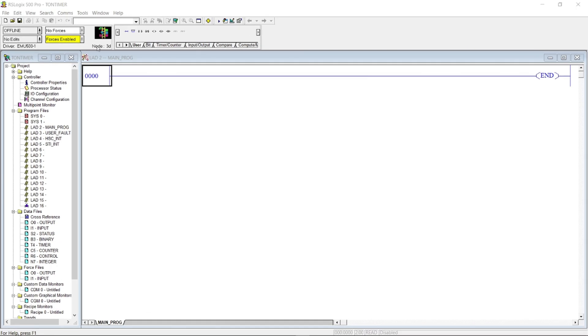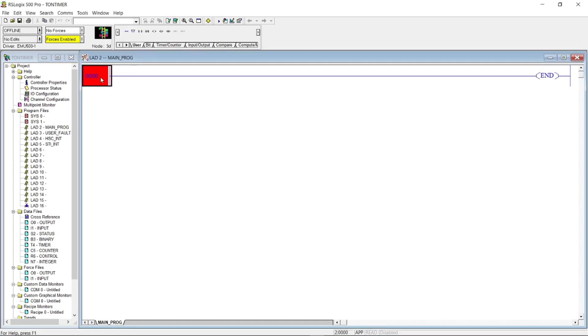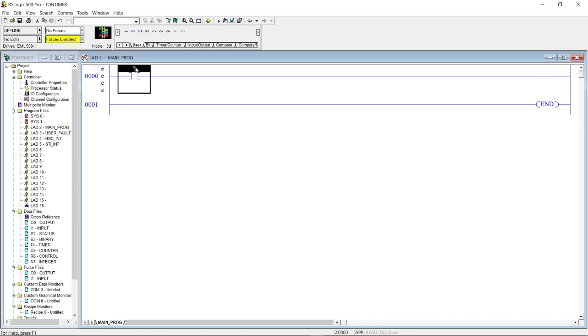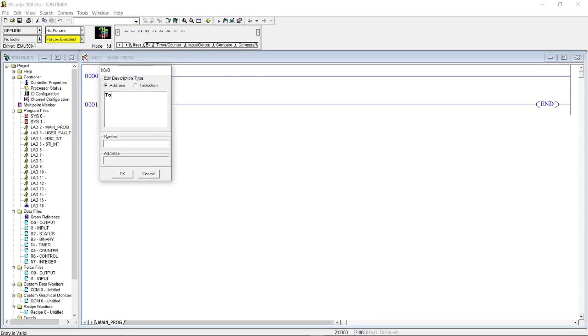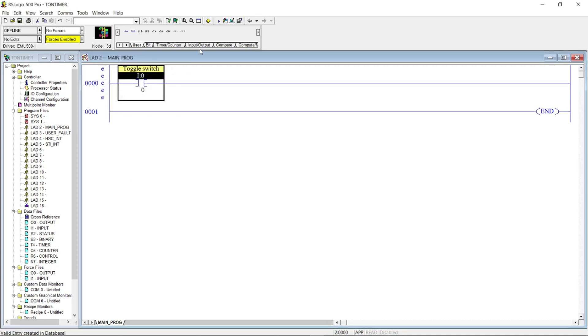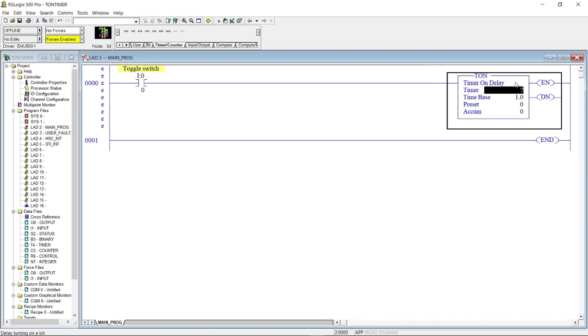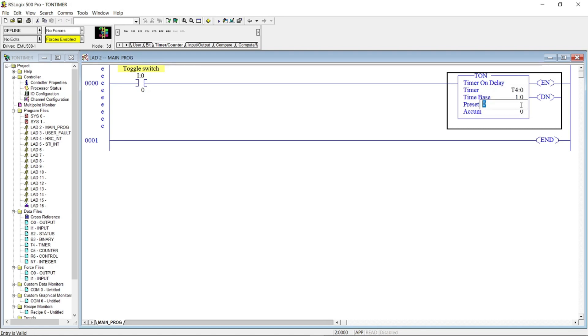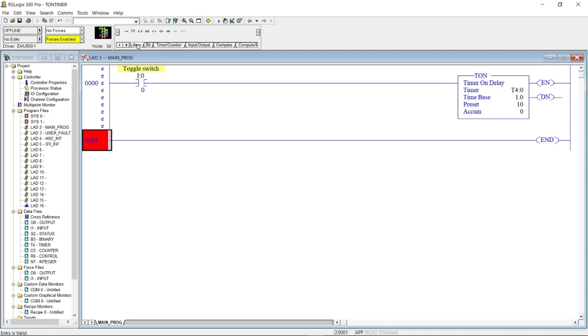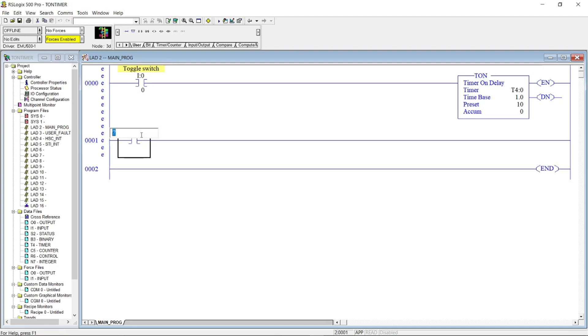Let's make a PLC program using the Timer On Delay. We'll put an open contact for a toggle switch, then drag in the Timer On Delay instruction. We will put the address for the timer as T4:0, and for the preset value we will put 10. This is the number of time increments that must count before changing the state of the output.